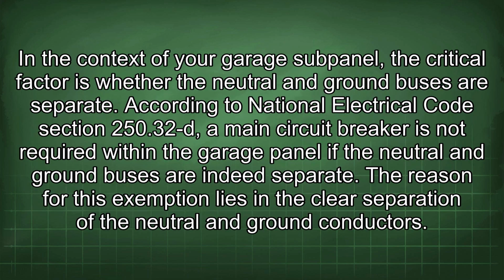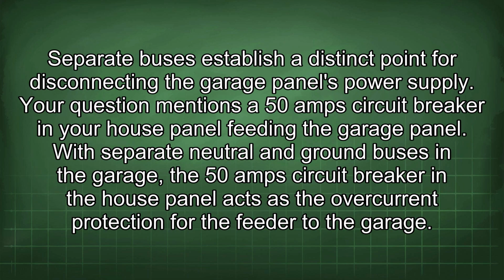In the context of your garage subpanel, the critical factor is whether the neutral and ground buses are separate. According to National Electrical Code Section 250.32(D), a main circuit breaker is not required within the garage panel if the neutral and ground buses are indeed separate. The reason for this exemption lies in the clear separation of the neutral and ground conductors. Separate buses establish a distinct point for disconnecting the garage panel's power supply.